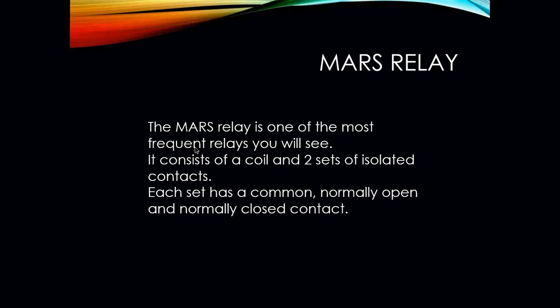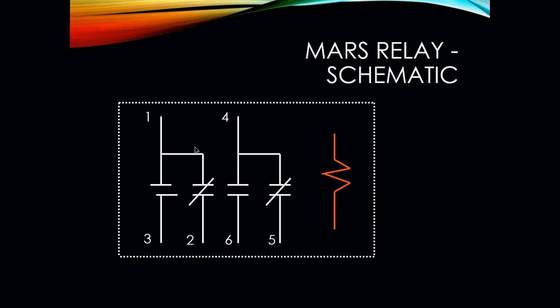Okay, the Mars relay is probably one of the most frequently used relays out there, and that's what you're most likely going to see a lot of. It consists of a coil and two sets of isolated contacts. Again, you're normally open and you're normally closed. Each set has a normally open and a normally closed contact. And if we were to look at a relay or a Mars relay, this is what we would kind of see. All of our designations are numbered. And if we were to look at it, we would actually have this very diagram on it.